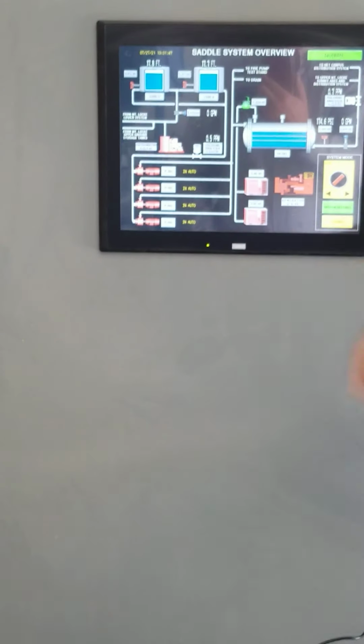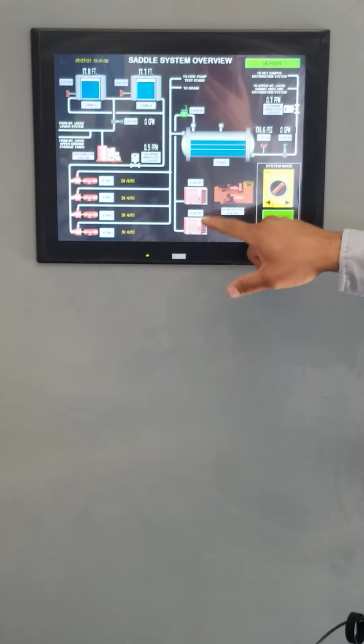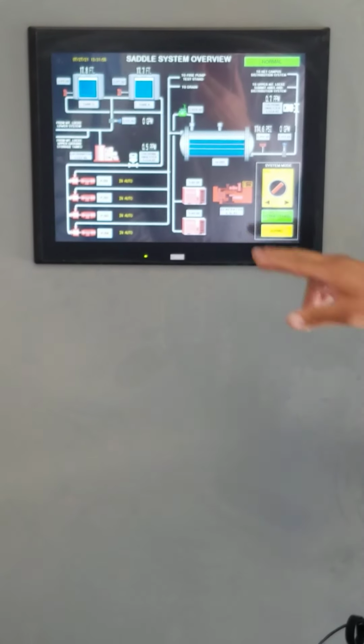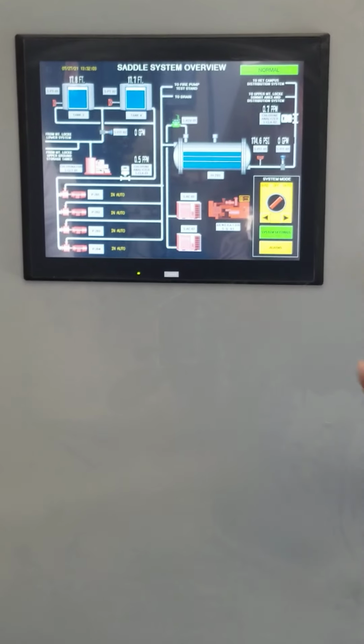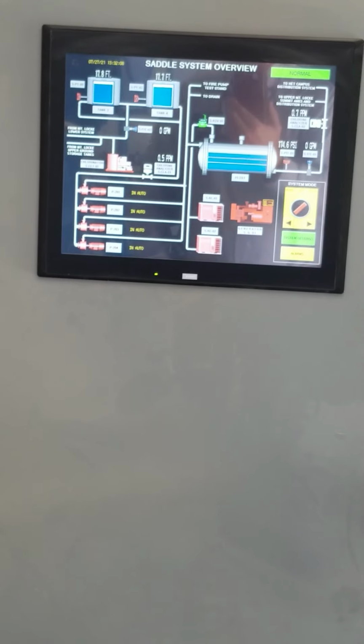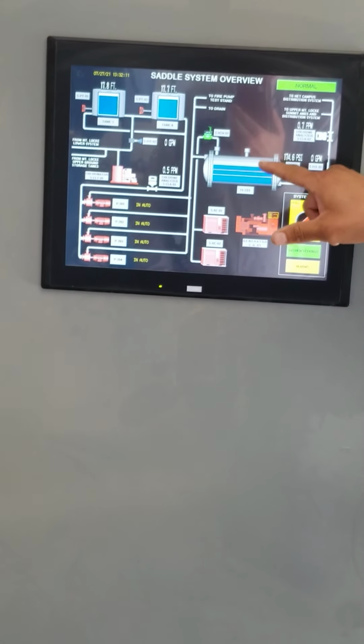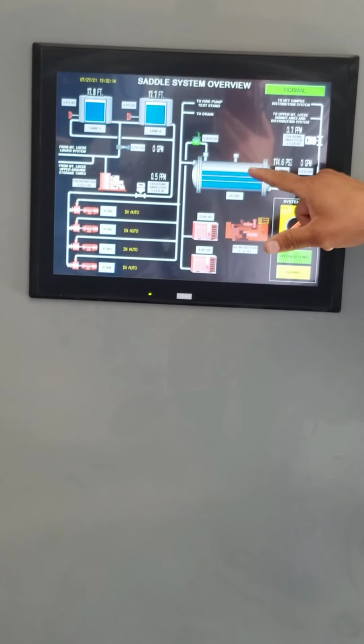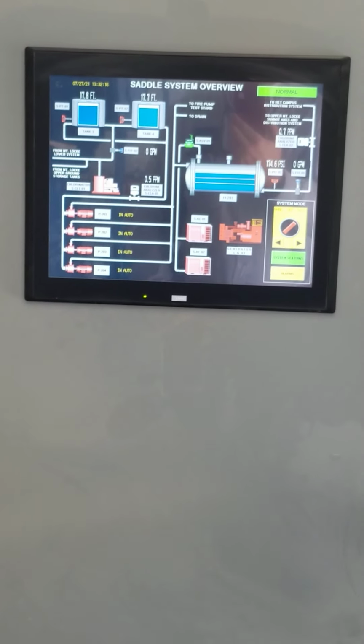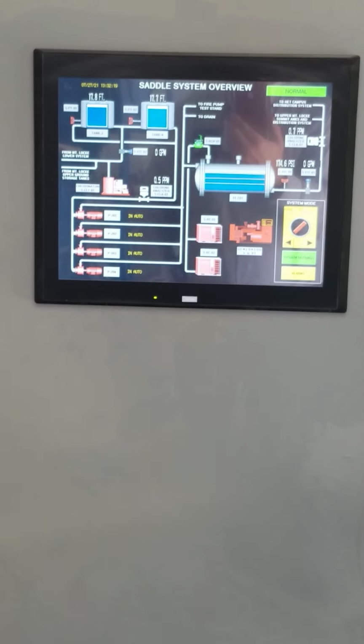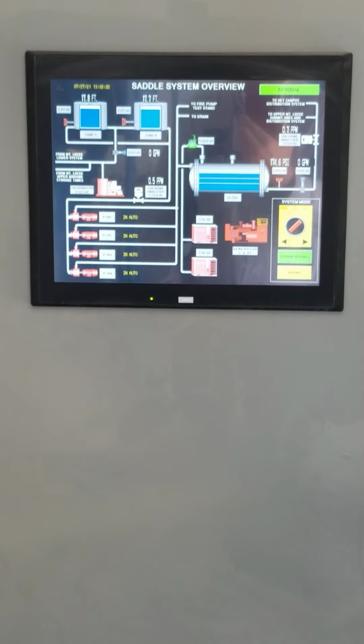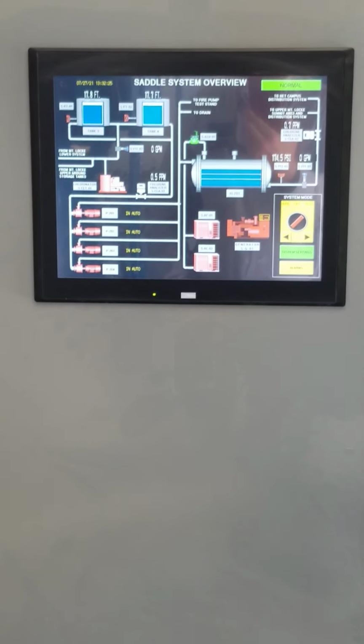In this section we have the 4 booster pumps, which you see on your back side. We have the 2 compressors here, compressor 1, compressor 2, and then their generator status. The only thing that we're going to get on the generator is run, that will turn green, or if there's a common alarm, will turn yellow. Red means off. We have a little picture here for a hydro pneumatic tank. We have 2 indications, which is the 2 probes. We have the add air on top. The middle one is to close the solenoid. And then the bottom one is just there's water in there. It's just a picture in there.